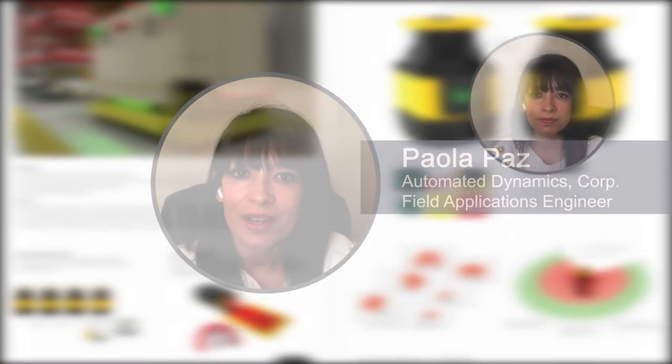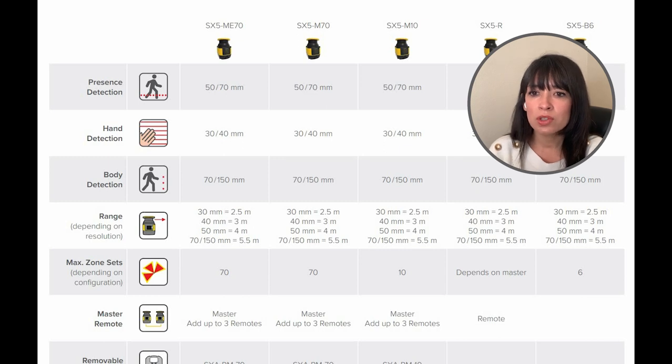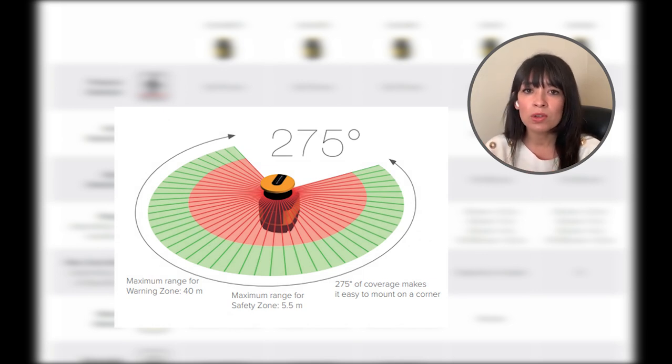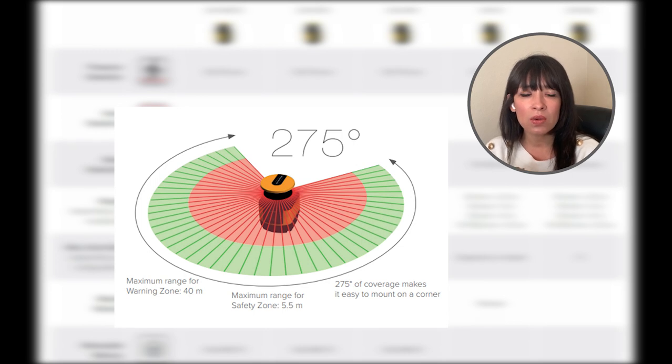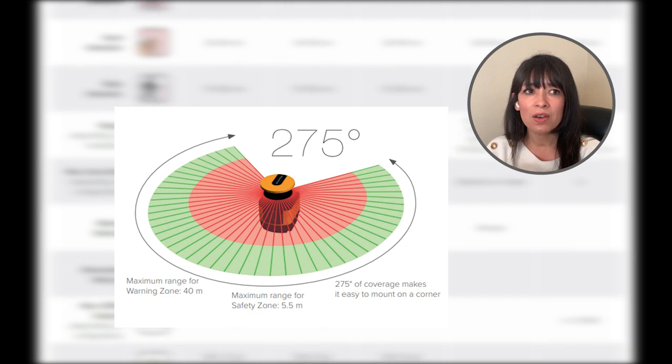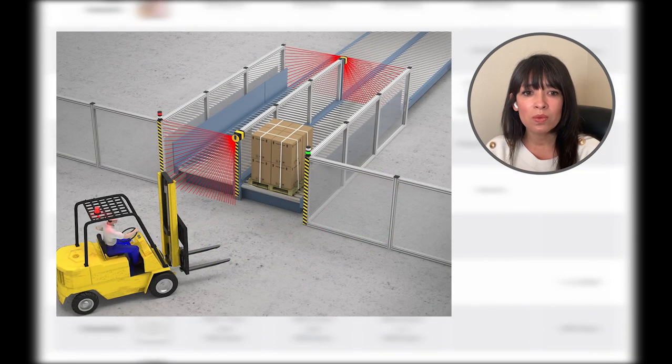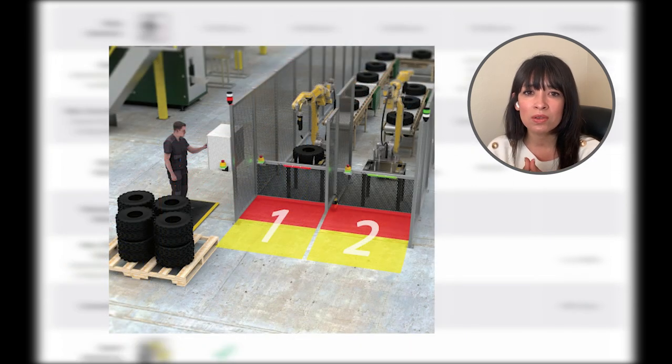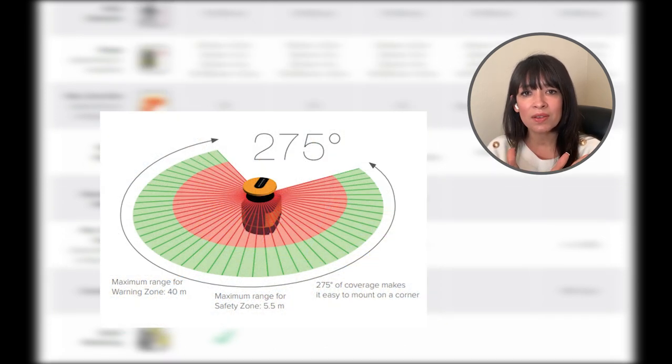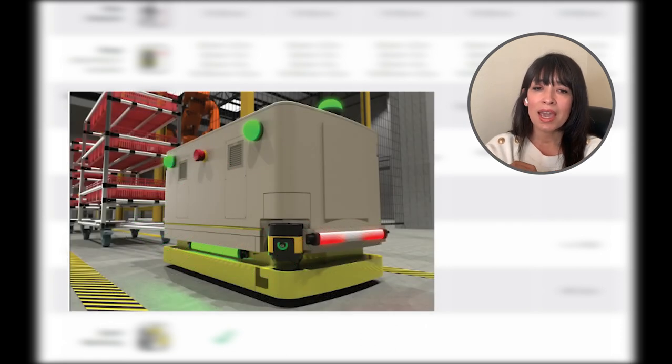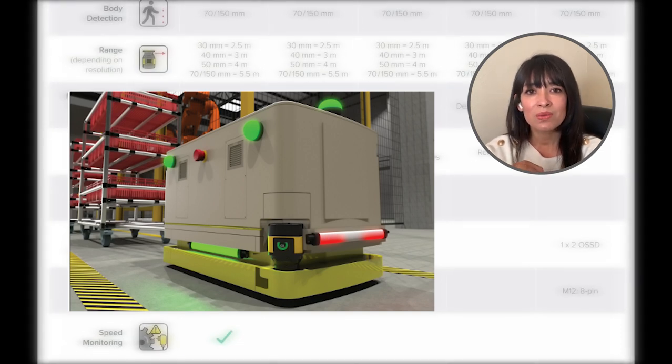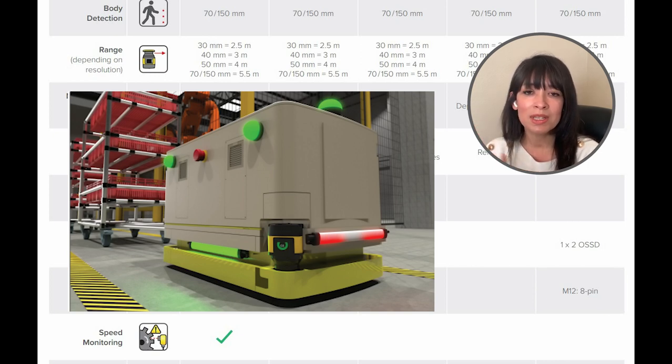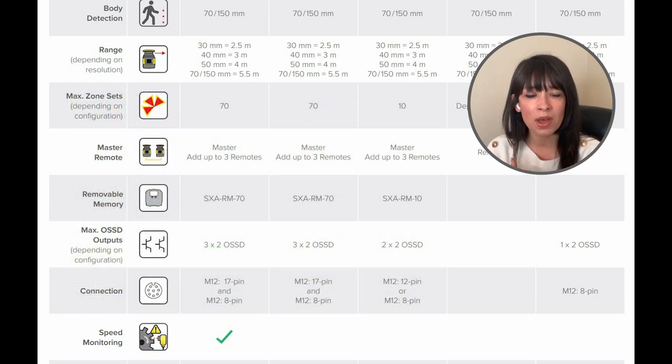As far as the hardware goes, it can do up to 5.5 meters within the safety zone and then it can go out to 40 meters in the warning zone. You can have multiple warning zones as well, and it has a really fast response time. You can have different safety zones for different zone type applications, and I'll post some videos here that kind of go over those specific applications. It has a 275 degree wide angle so you can actually protect an entire corner, whereas some other more limited range competitors you might actually have to have multiple safety scanners. Ultimately, having that wide angle can save you some money on your application as well.